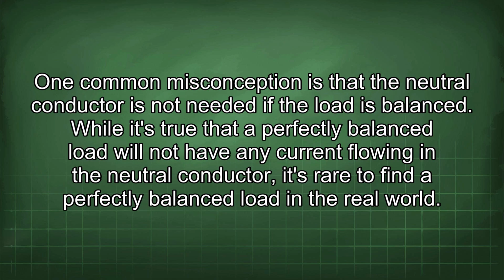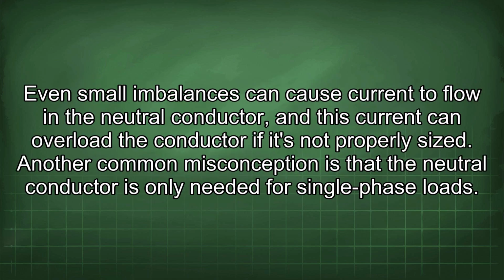While it's true that a perfectly balanced load will not have any current flowing in the neutral conductor, it's rare to find a perfectly balanced load in the real world. Even small imbalances can cause current to flow in the neutral conductor, and this current can overload the conductor if it's not properly sized. Another common misconception is that the neutral conductor is only needed for single-phase loads.